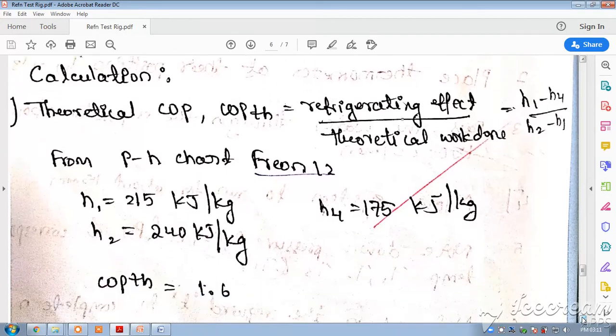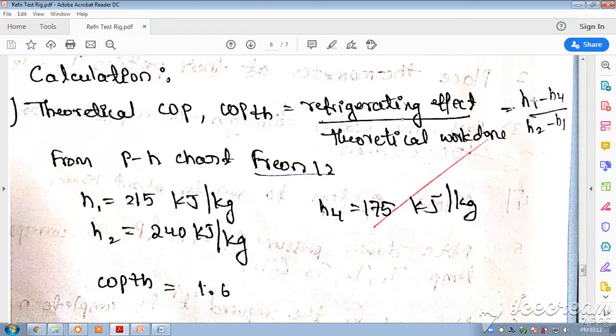Then the theoretical COP is the refrigeration effect: H1 minus H4 divided by H2 minus H1, where these are the enthalpies. So the refrigeration effect is H1 minus H4 and the compressor work is H2 minus H1.